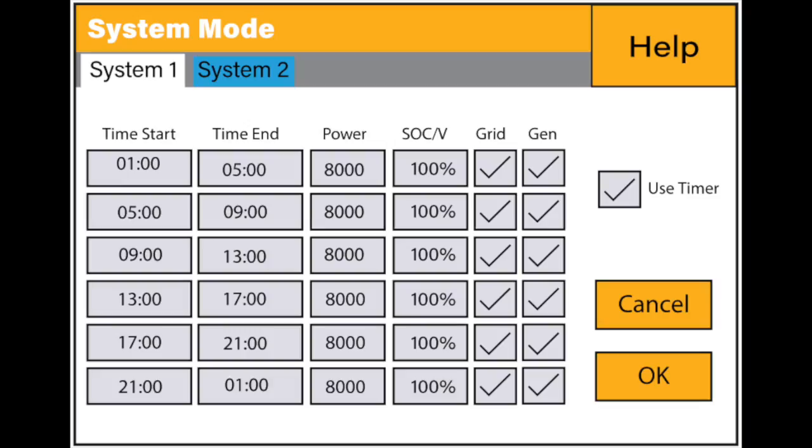I must mention that SunSync inverters are usually very reliable but the problem I had with this particular unit was that the settings applied in system mode 2 was not working as programmed. The unit had time of use settings for the full 24 hours with varying SoCs for each time slot but the inverter was ignoring these settings.